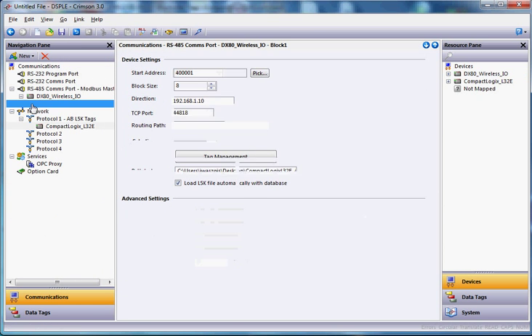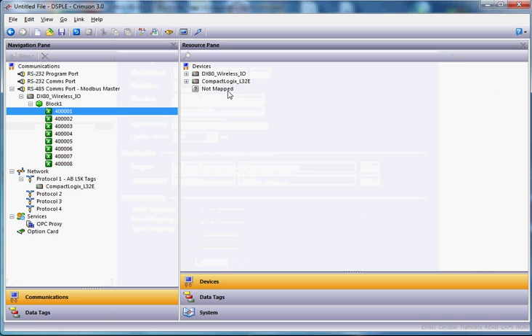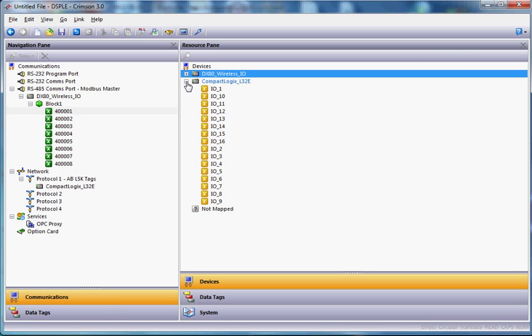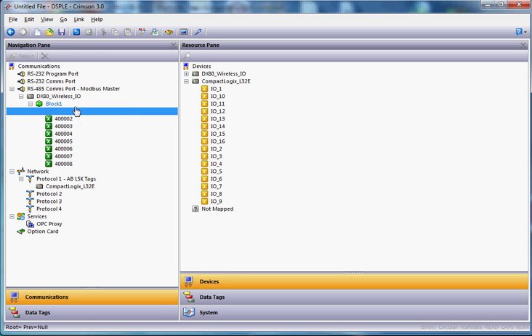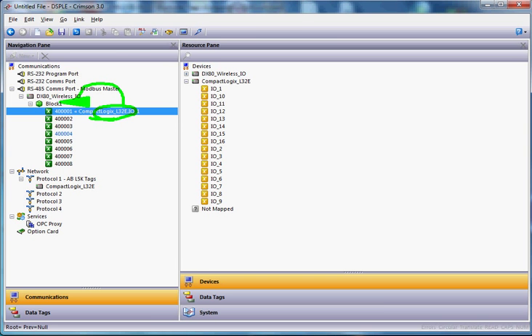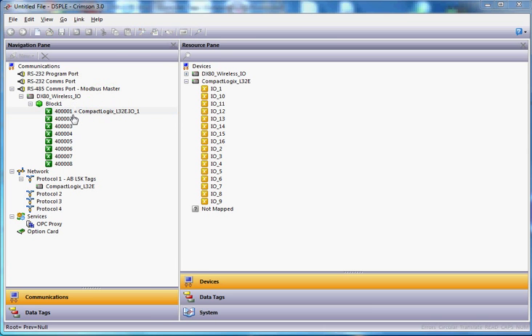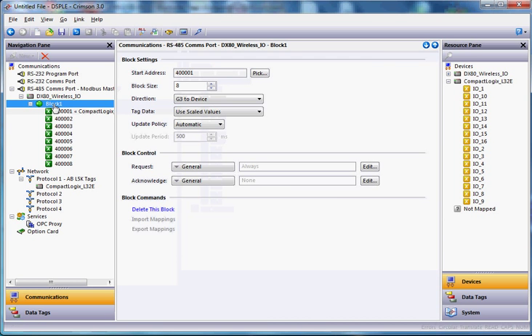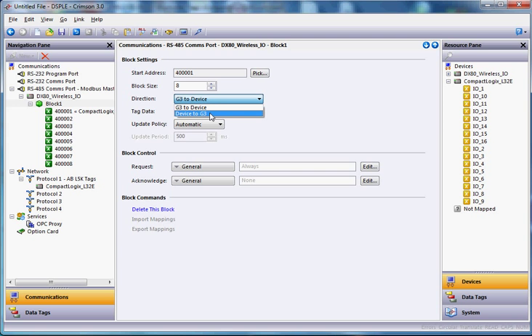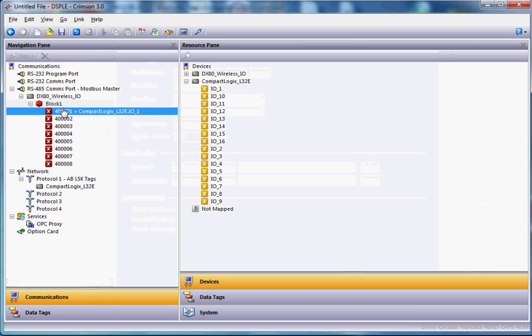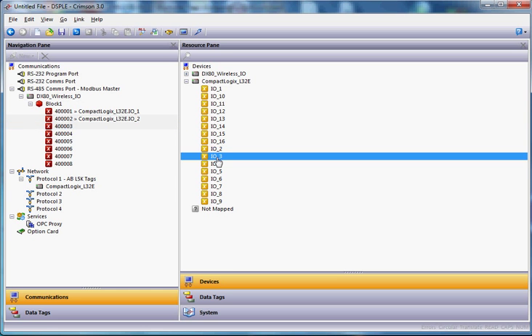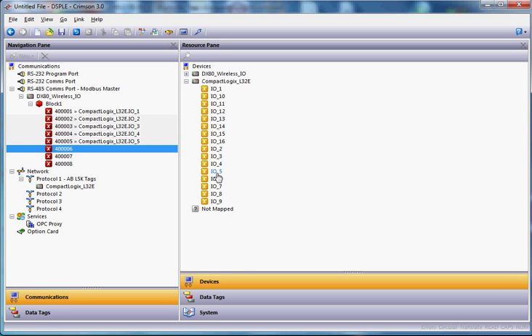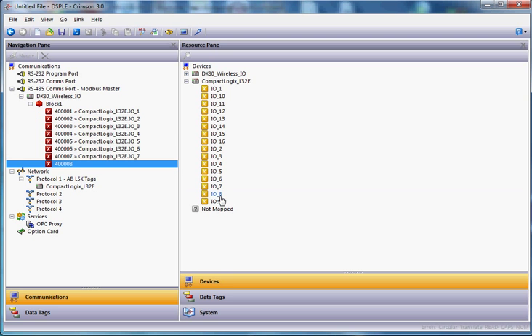Now if we go back over to here, expand this, click on this first guy, now I should be able to expand my Allen Bradley. So if I take this one right here, drag it right here, notice the little arrow right here. If you see there's an arrow right here. The arrow's actually going this way. It's going to take this value and put it into here. Well, that's not the right way. It needs to go the other way. So if I hit the Block 1 right here and where it says Direction, hit the pulldown, choose Device to G3. Now if you look, guys, you'll see the arrow's actually going this way. It's going from here into here, which is exactly what I want to do. So then I'll just take this guy and I'll click here. Number two's there. Number three's the next guy. Okay, four's next, five's there. And there's number eight. That covers all the input data.